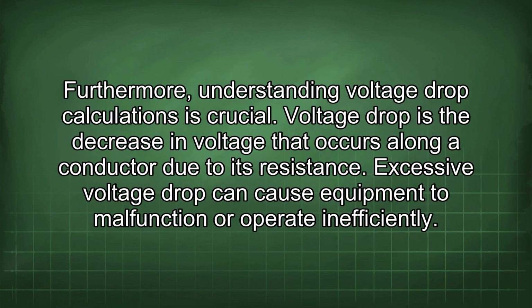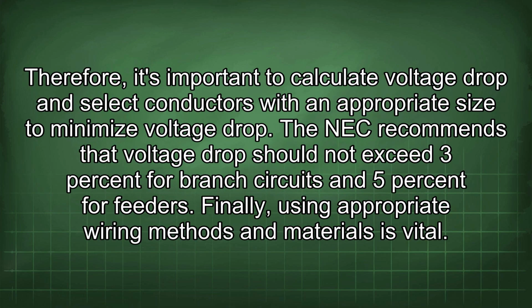Furthermore, understanding voltage drop calculations is crucial. Voltage drop is the decrease in voltage that occurs along a conductor due to its resistance. Excessive voltage drop can cause equipment to malfunction or operate inefficiently. Therefore, it's important to calculate voltage drop and select conductors with an appropriate size to minimize voltage drop. The NEC recommends that voltage drop should not exceed 3% for branch circuits and 5% for feeders.